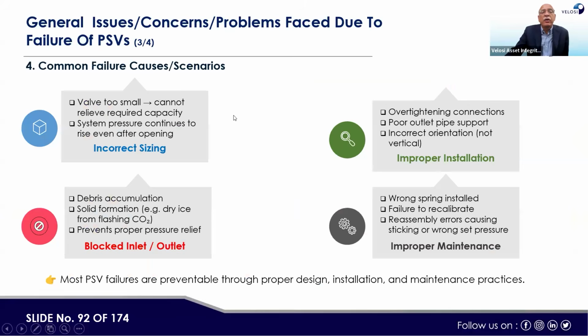Common failure causes and scenarios: number one, for example, the valve is too small and cannot relieve the required capacity, so system pressure continues to rise above the operating pressure. Number two, if the fluid service is not correct, debris accumulation and solid formation prevent proper pressure relief. Then over-tightening connections, poor outlet piping support, incorrect orientation, not vertical, a wrong spring installed, failure to recalibrate, and reassembly error causing sticking or the wrong set pressure.